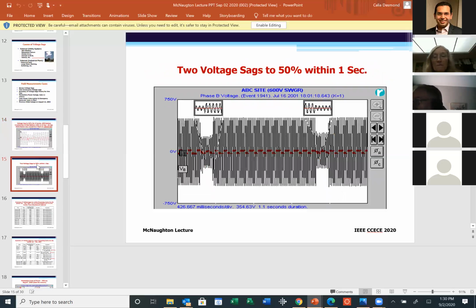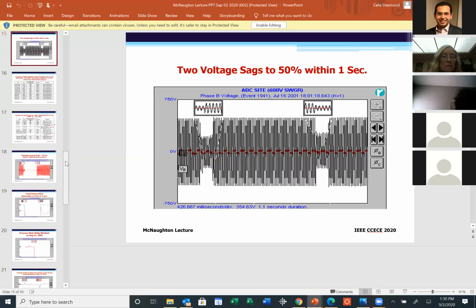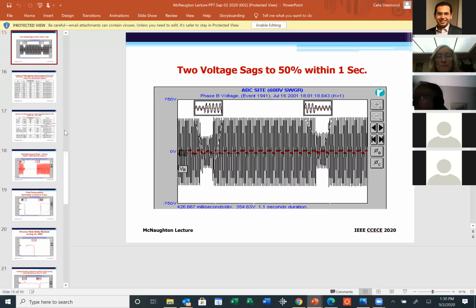What is interesting here, you can see 2 voltage sags that took place within a 1 second window. Naturally, in this situation, this is normally caused by what we call, in our technical jargon, auto-reclosure. The utility has breakers, electrical devices, and when there is a fault on their line, that breaker will trip. And then, in order to restore the power very fast to the customer, they reclose. Typically they reclose within 1 second. And so this would happen. And then, as you can see, there was a second fault. Next slide, please.